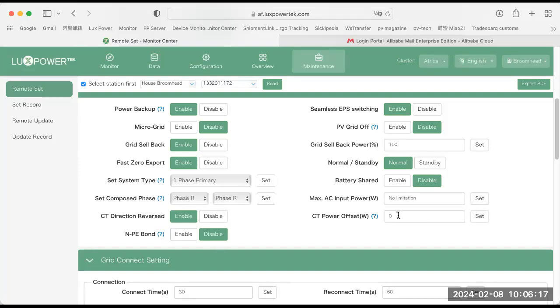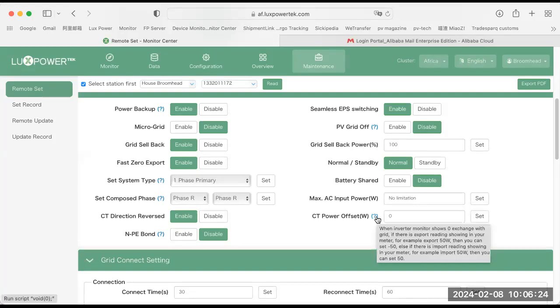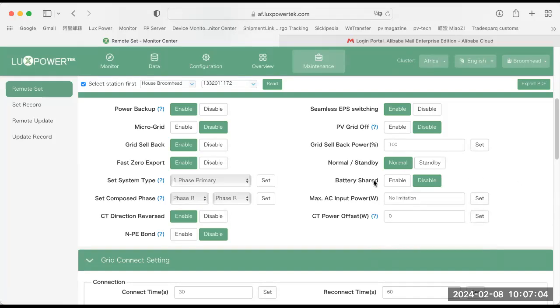All right. CT offset power. We spoke about this a little bit earlier. If you click on the question mark, you will see how low you can go. Minus 50. That cannot be true. No, this is the LXP5. Okay. Yeah. So on the CT offset, if you want to know what the feature does, and I know Joe's going to be updating these messages on the question marks, simply hover over the blue question mark, and it'll tell you what the button will do. So if you've got that famous BEC23 Conlog meter, you can simply do your CT offset here, just like you can do it on the SNA. But here you've got a much higher value on the LXP5.